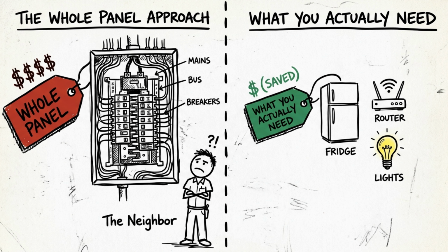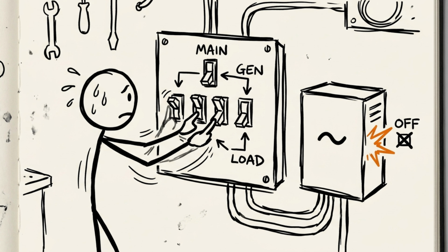The commercial whole home backup pitch hides the same assumption in reverse. It's sized and priced for the panel's theoretical maximum draw when you were only ever going to run the fridge, the router, and a few lights. A manual transfer switch is legally allowed to rely on you, the human, to only turn on what the inverter can handle at once. Skip that judgment call, overload the inverter, and it shuts itself down mid-outage. None of this is a battery problem. It's a switch and sizing problem, and almost nobody frames it that way.